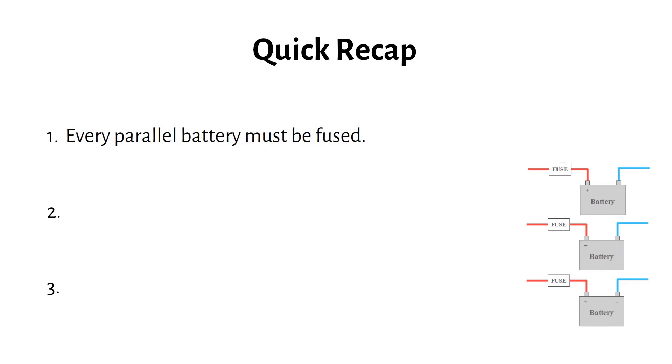Before we dive into the setups, here are three things you need to know. First, every parallel battery must be fused. Here's why. If one battery develops a fault, it can dump its entire short-circuit current into your other batteries. Fusing each battery prevents this dangerous situation.